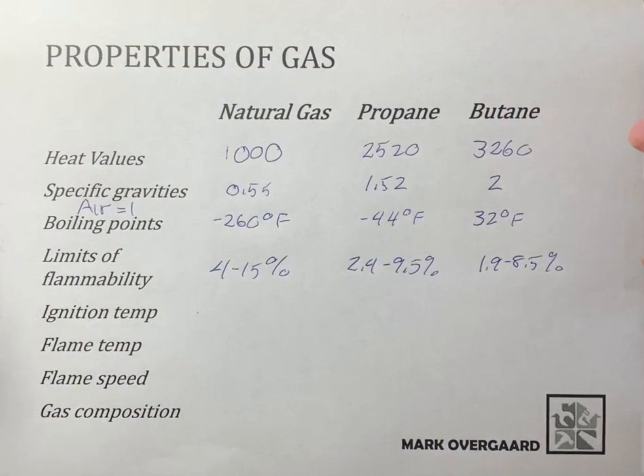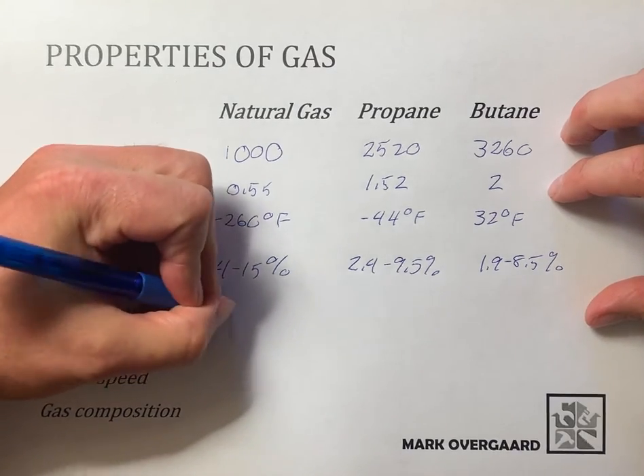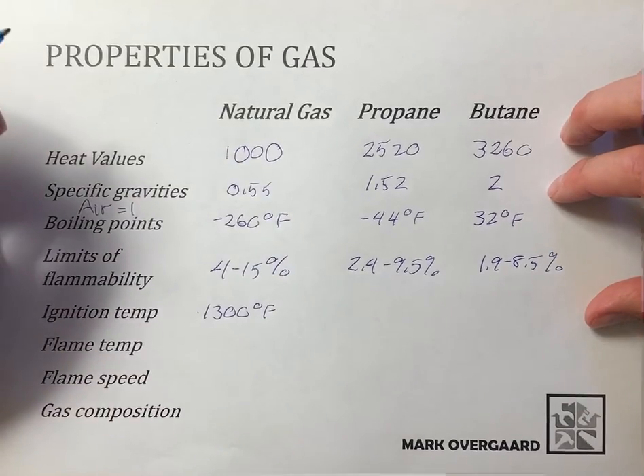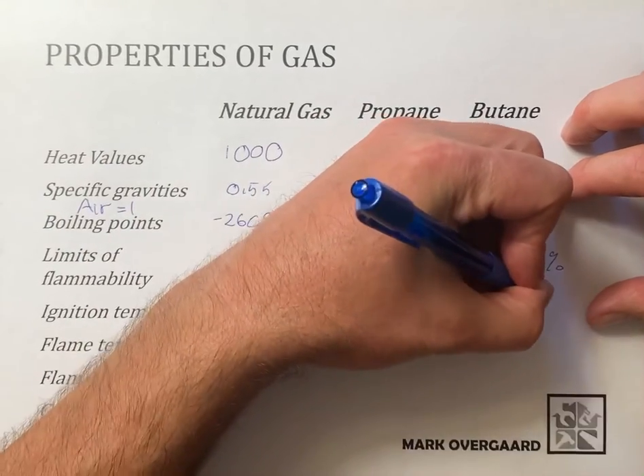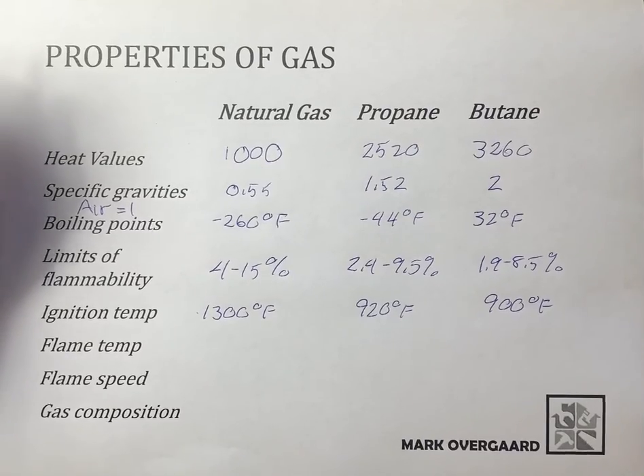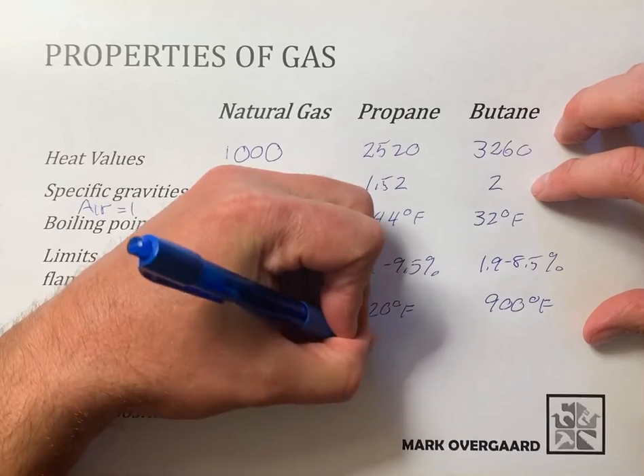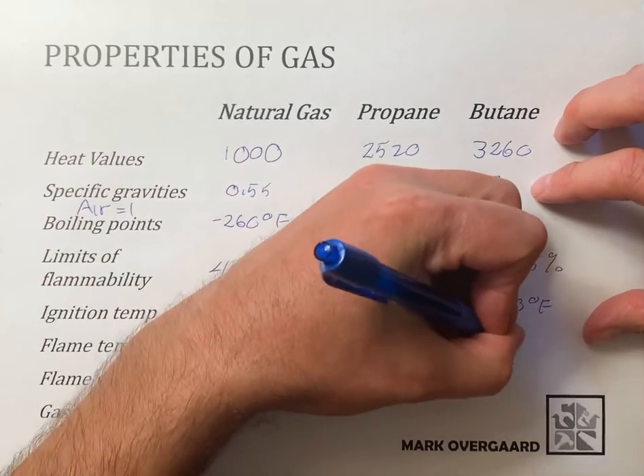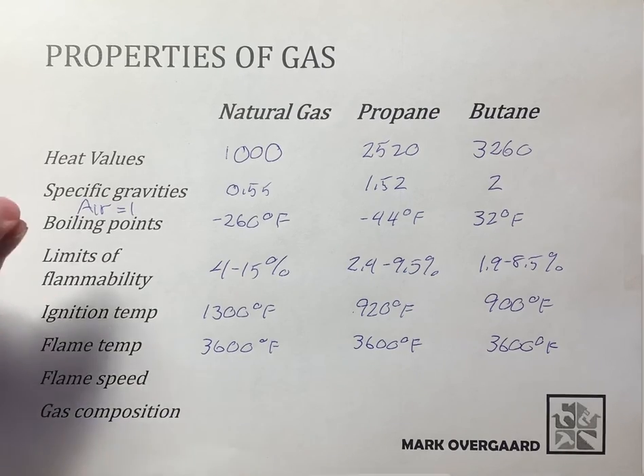Ignition temperature — this is what you need from some type of heat source, a spark, a hot surface igniter, or flame, to light the gas. For natural gas it's 1,300°F. Propane is 920°F, and butane is 900°F. Now, what does the flame temperature come up to? For all three gases it's exactly the same: 3,600°F. These are all in Fahrenheit; you can find Celsius equivalents in the metric tables in Annex I.